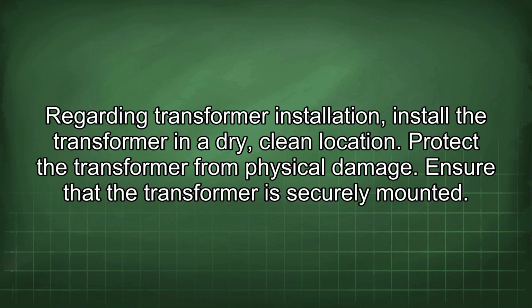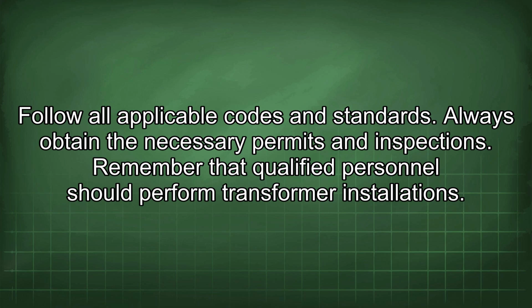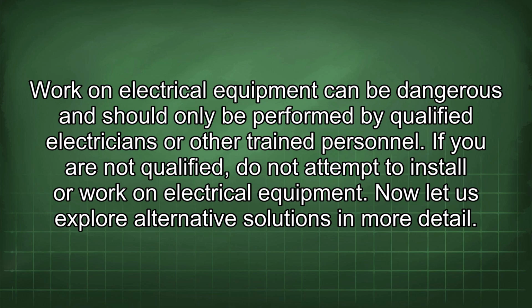Regarding transformer installation, install the transformer in a dry, clean location. Protect the transformer from physical damage. Ensure that the transformer is securely mounted. Follow all applicable codes and standards. Always obtain the necessary permits and inspections. Remember that qualified personnel should perform transformer installations. Work on electrical equipment can be dangerous and should only be performed by qualified electricians or other trained personnel. If you are not qualified, do not attempt to install or work on electrical equipment.